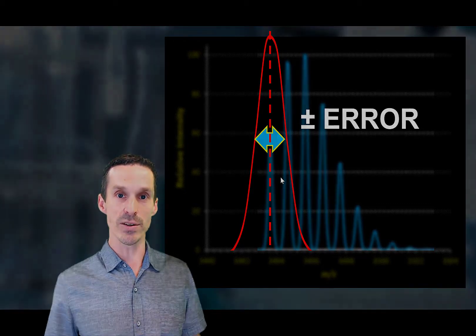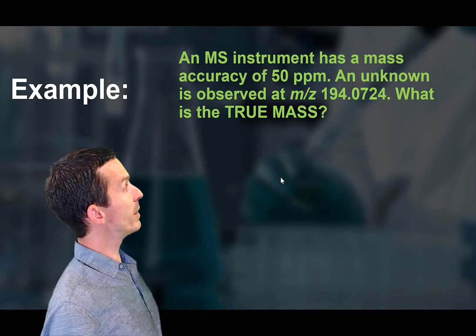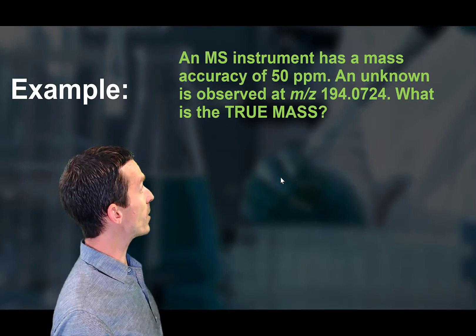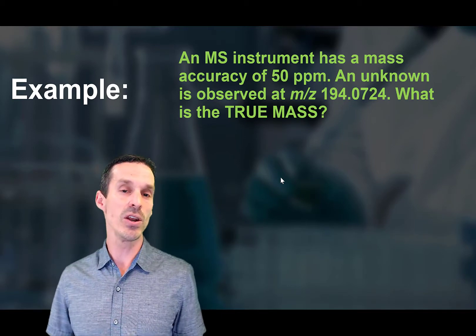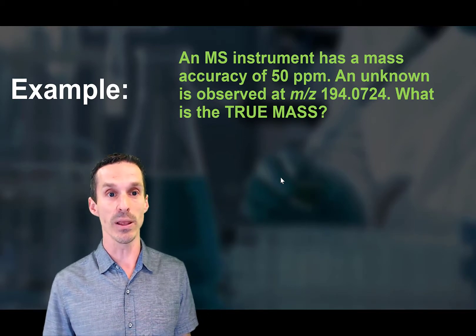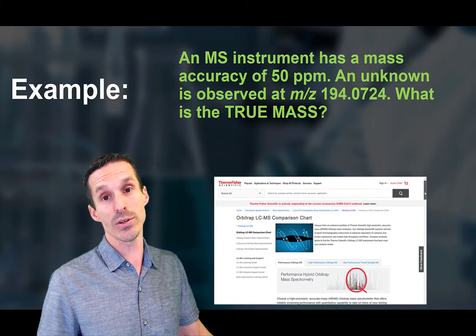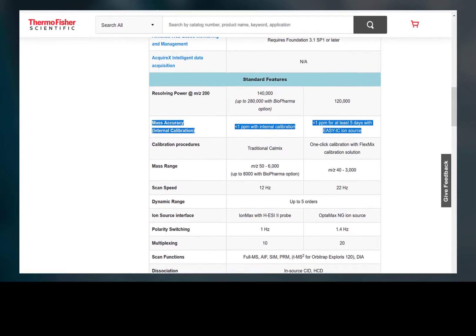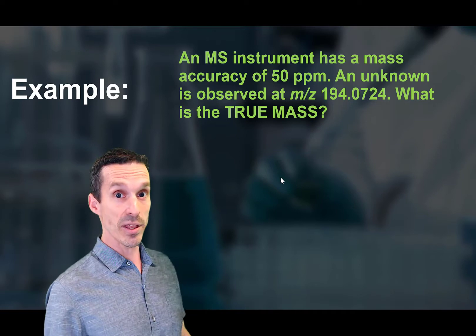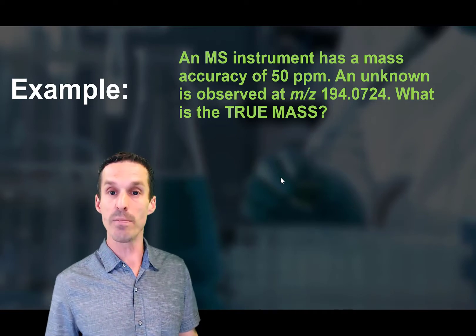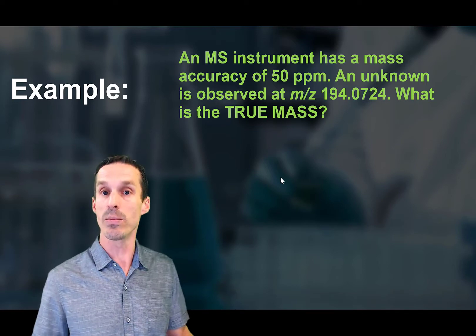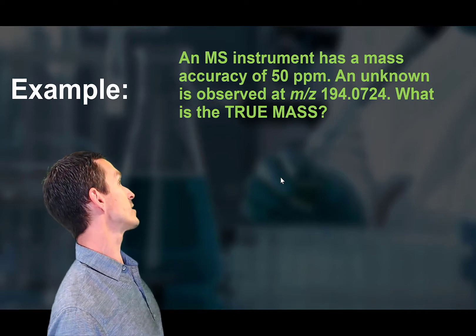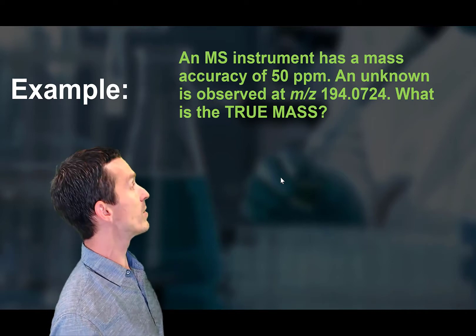Let's just do an example to kind of drive this home. Okay, so in this example here, we have a mass spectrometer and it provides us with a mass accuracy of 50 parts per million. And just pause for a second. How would you even know that the mass spectrometer provides 50 parts per million? Well, one of two ways, actually. First, usually the instrument manufacturers are going to tell you, hey, our mass spectrometers are good to 50 parts per million. That's pretty good. And the other thing that you could do is just check it out for yourself. So take a compound that you know the mass and start measuring it. You'll see that the numbers are going to vary a little bit. So back to the question, we take our unknown and we read it and it just gives us a mass of 194.0724.